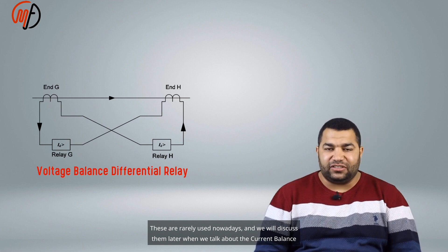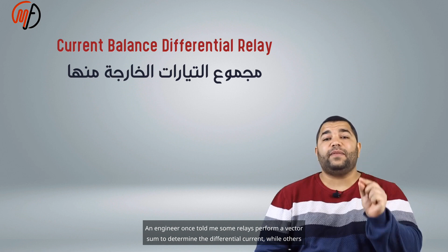Normally, the sum of currents entering a point equals the sum leaving it, making the differential current ideally 0. Sum of currents refers to the vector sum, considering both magnitude and direction. An engineer once told me some relays perform a vector sum to determine the differential current, while others subtract it. This is incorrect. All relays perform a vector summation to find the differential current.